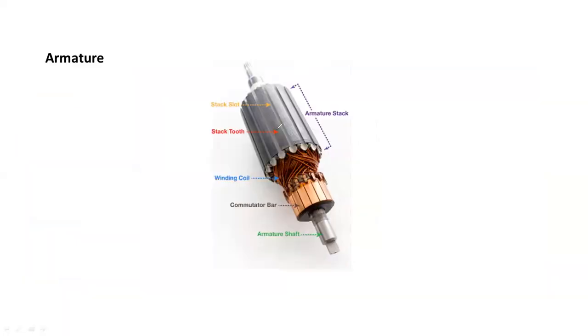Here you can see the structure of armature — it is made up of n number of slots. The entire segment is generally called as armature. It is made up in a laminated fashion to minimize eddy current loss. Eddy current loss should be as minimum as possible; otherwise efficiency comes down.